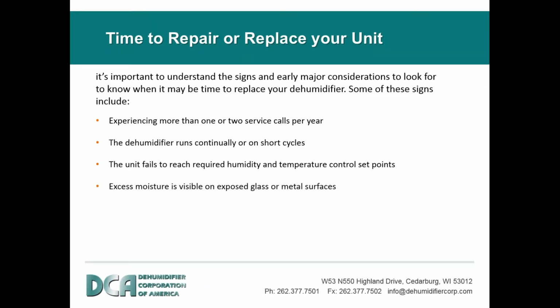Excessive moisture is visible on exposed glass or metal surfaces. Normally in very, very cold climates where the temperature is below 0 outdoors, you can expect some moisture forming on the glass. The moisture buildup point is about 65 degrees, and of course keeping glass in very cold climates at 65 degrees is very hard to do. But when you see it on metal surfaces, that's another giveaway that the humidity moisture is building up.